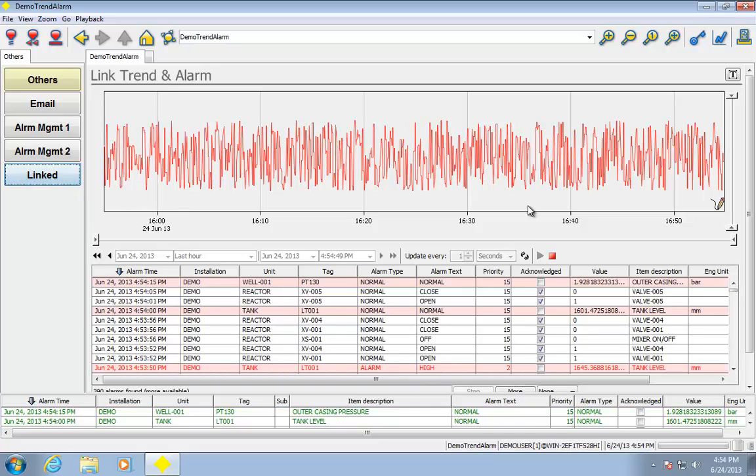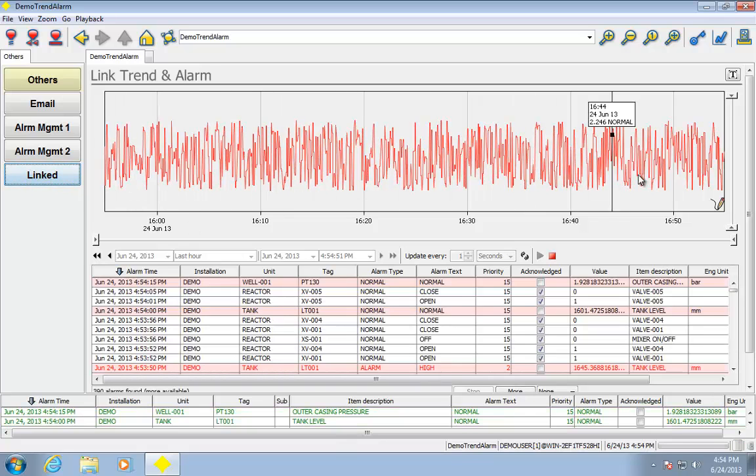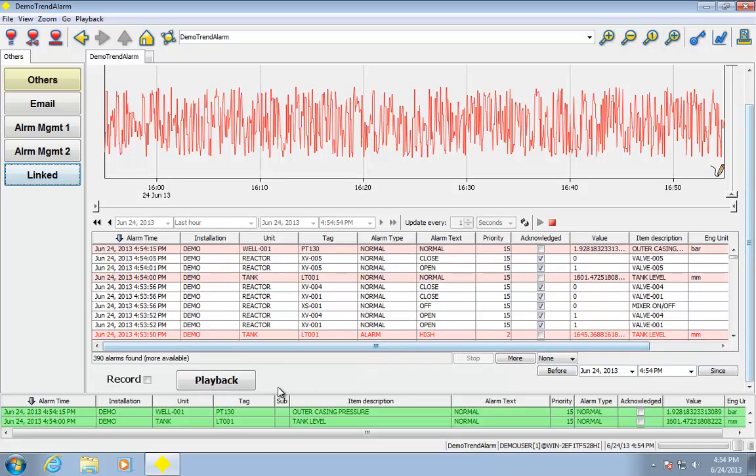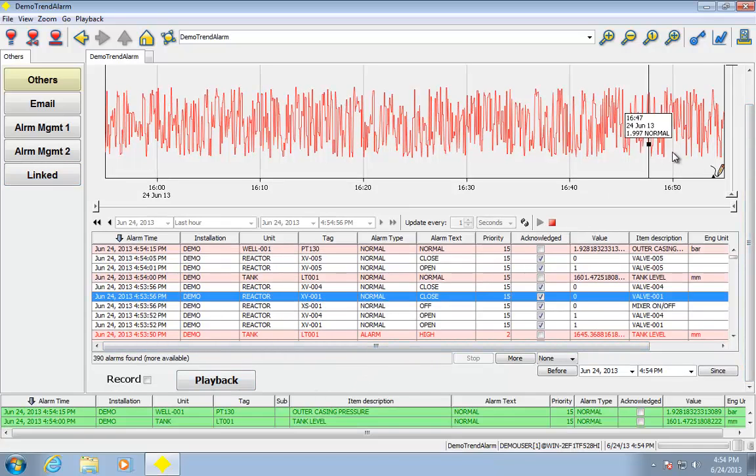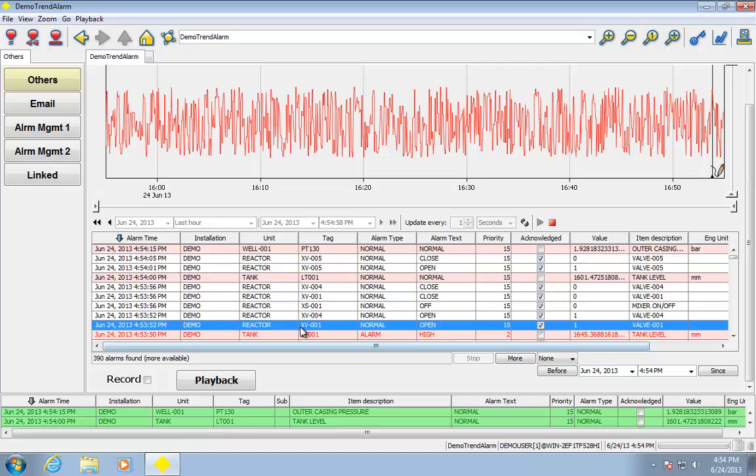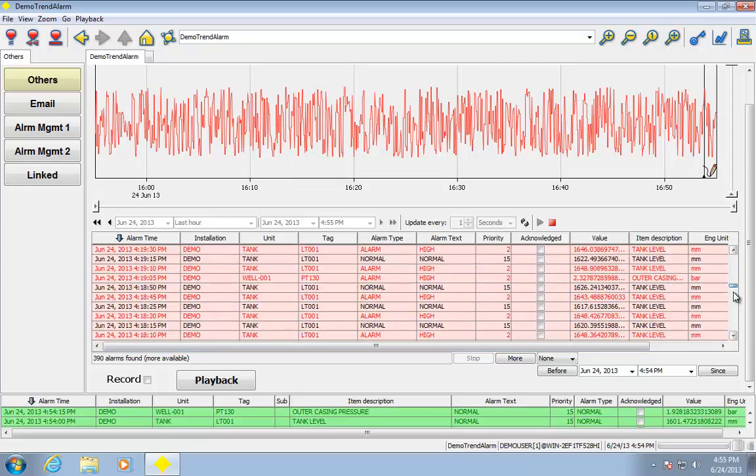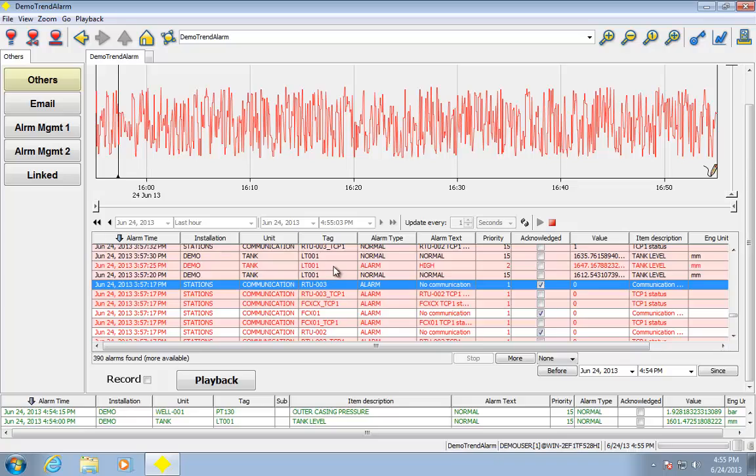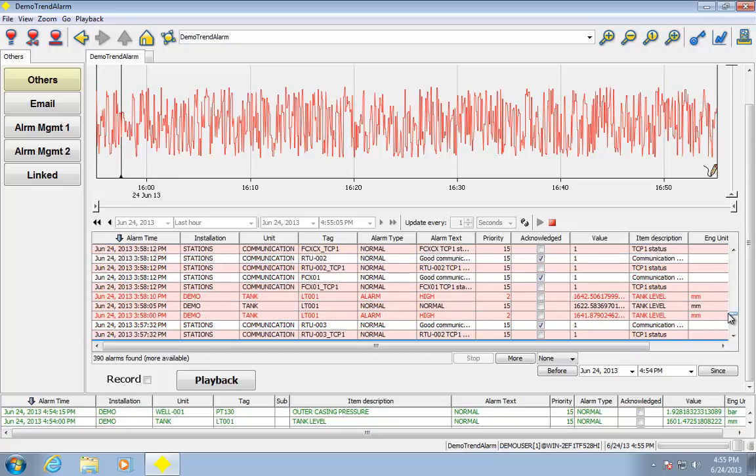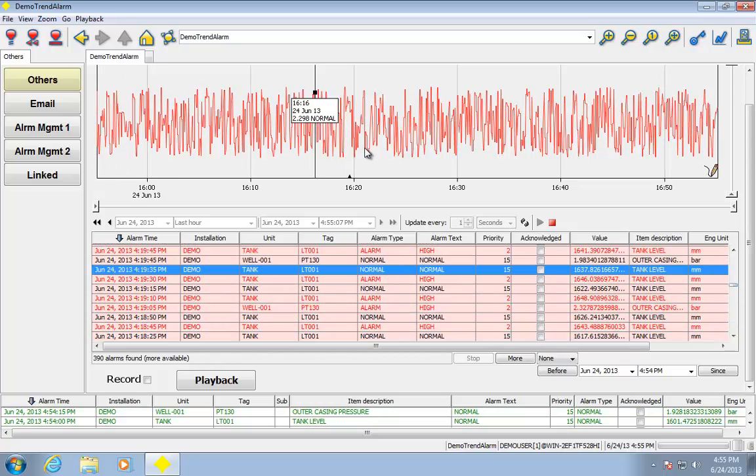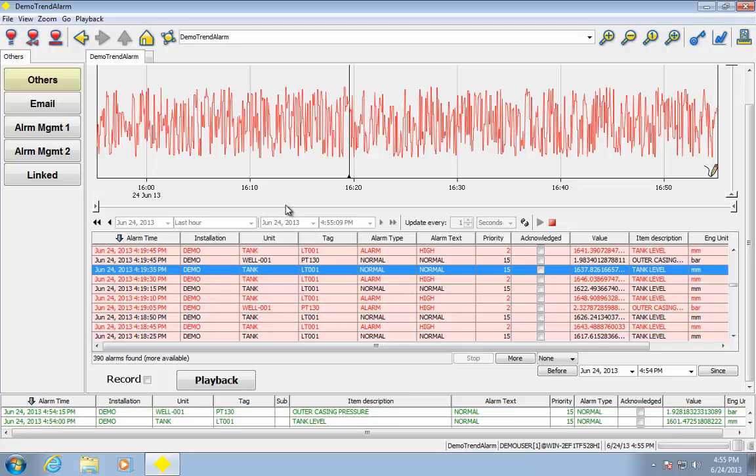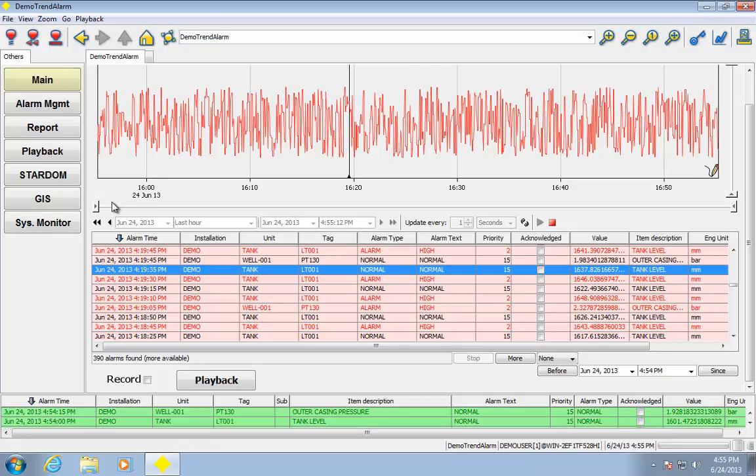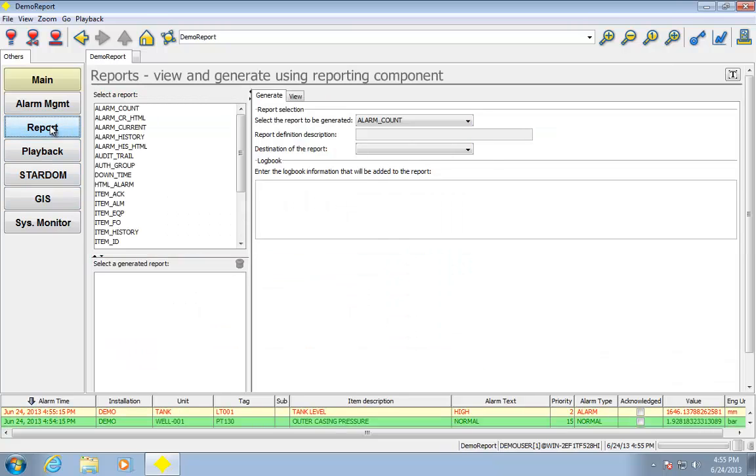This is kind of an interesting one. So I've got a process variable trending across here. I can go ahead and click and you'll see a little cursor show up wherever I click. So I can see on that trend exactly where that alarm happened. So that's what we call alarm linking there.